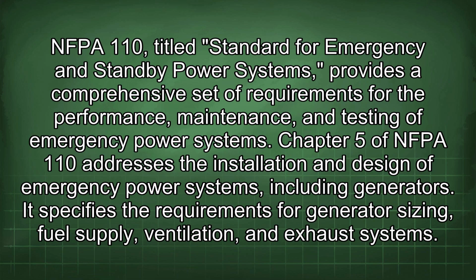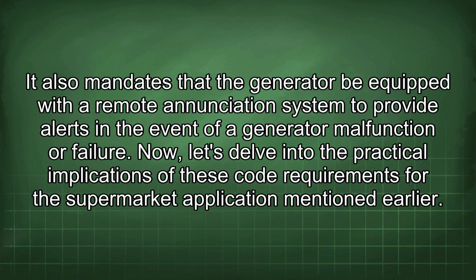NFPA 110, titled Standard for Emergency and Standby Power Systems, provides a comprehensive set of requirements for the performance, maintenance, and testing of emergency power systems. Chapter 5 of NFPA 110 addresses the installation and design of emergency power systems, including generators. It specifies the requirements for generator sizing, fuel supply, ventilation, and exhaust systems. It also mandates that the generator be equipped with a remote annunciation system to provide alerts in the event of a generator malfunction or failure.